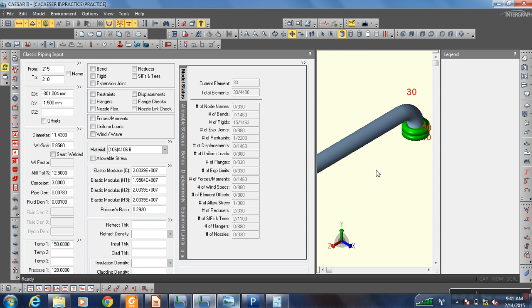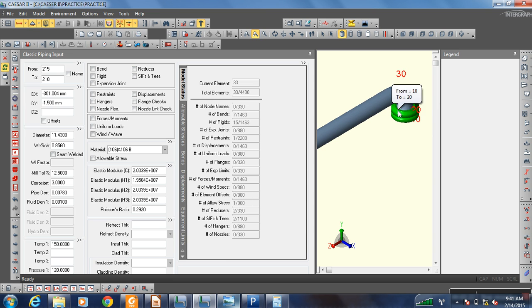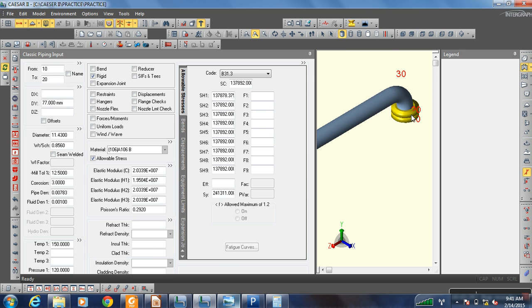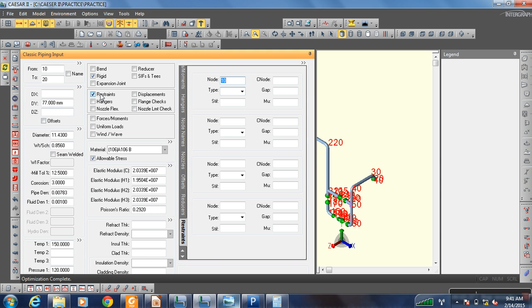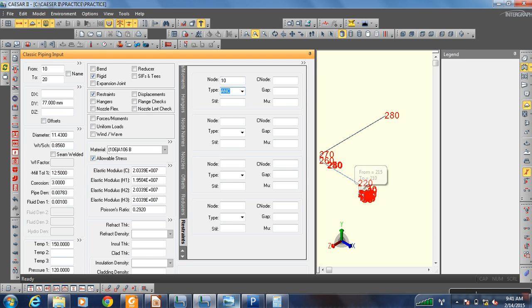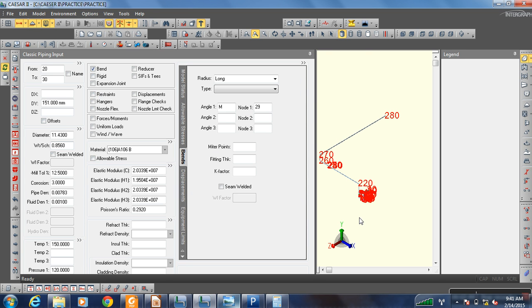Now come to the nozzle part. This flange will be connected to a flange of some pump or something, so it should not move. In order to fix this in all directions, apply a restraint anchor — the anchor will stop it from moving in all directions.